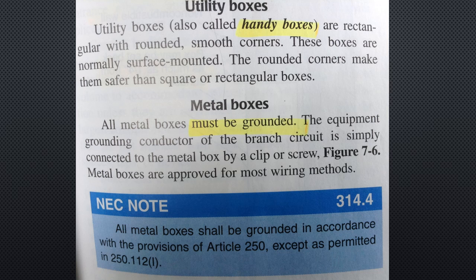Metal boxes: all metal boxes must be grounded. The equipment grounding conductor of the branch circuit is simply connected to the metal box by a clip or screw. Figure 7-6 shows a good example of this, which will show here momentarily. Metal boxes are approved for most wiring methods. NEC note 314.4: all metal boxes shall be grounded in accordance with the provisions of Article 250, except as permitted in 250.112.I.